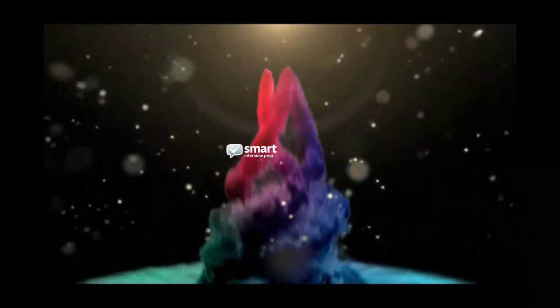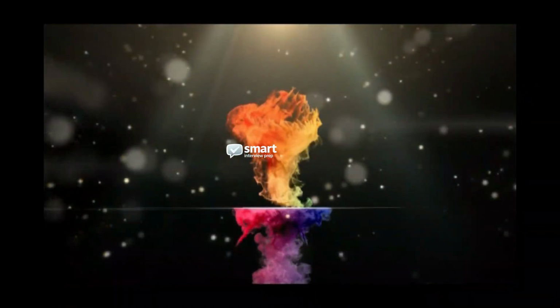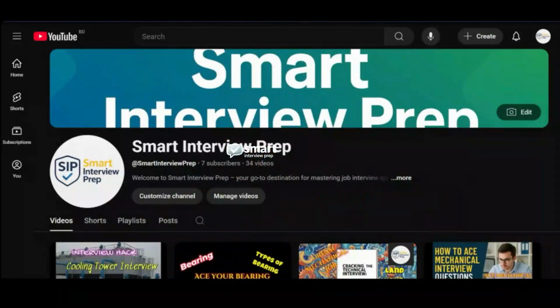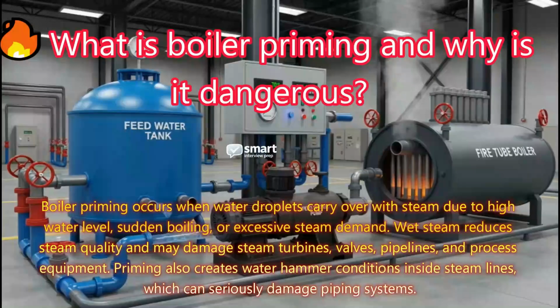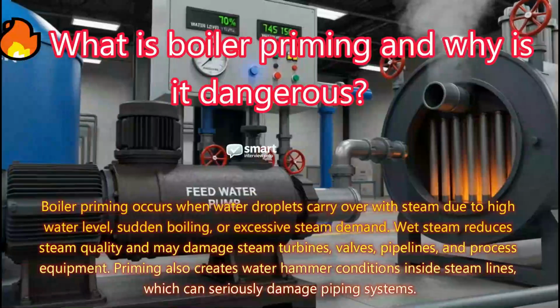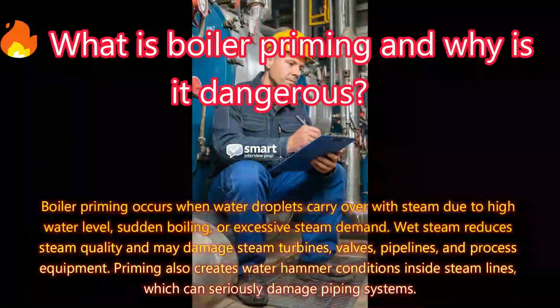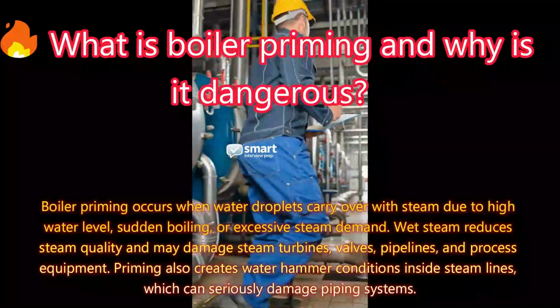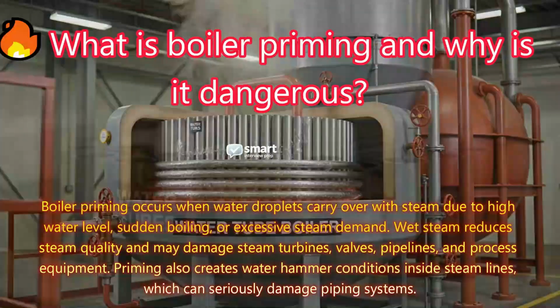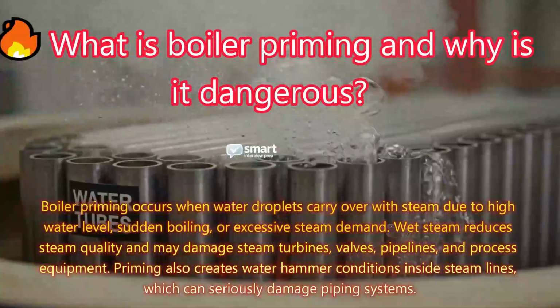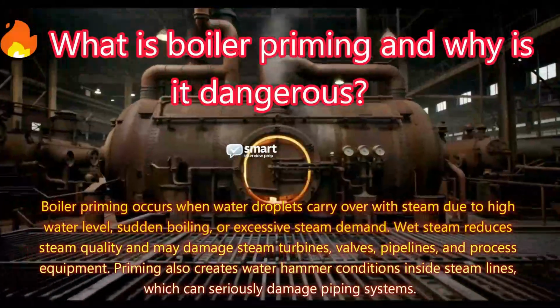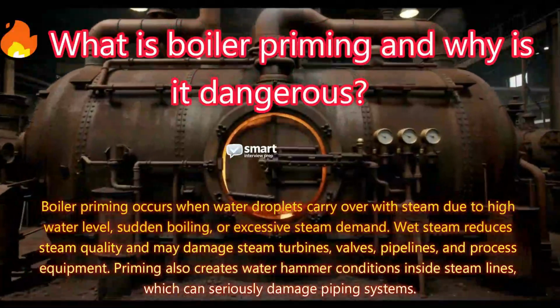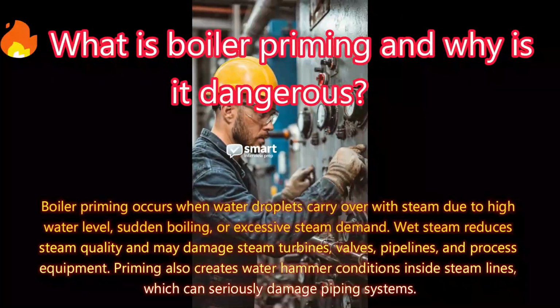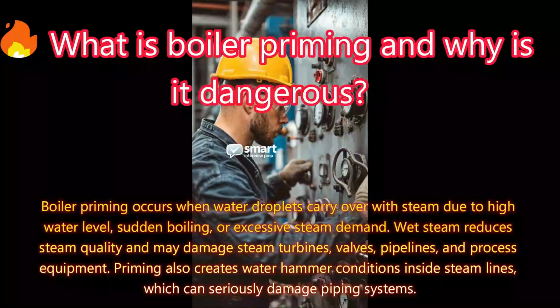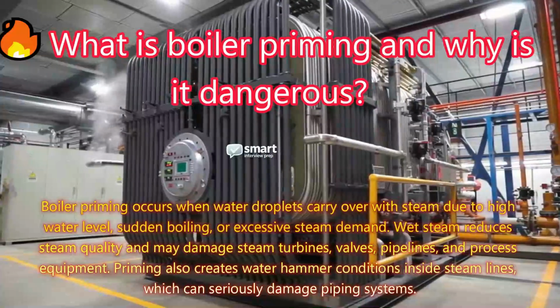What is boiler priming and why is it dangerous? Answer. Boiler priming occurs when water droplets carry over with steam due to high water level, sudden boiling, or excessive steam demand. Wet steam reduces steam quality and may damage steam turbines, valves, pipelines, and process equipment. Priming also creates water hammer conditions inside steam lines, which can seriously damage piping systems.